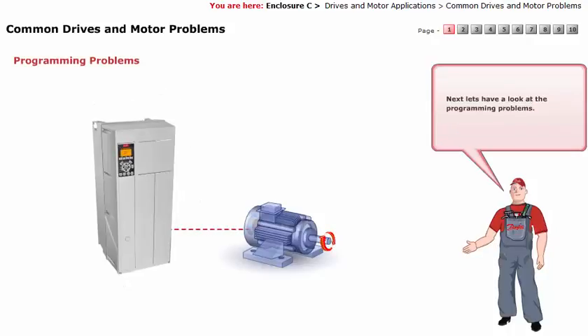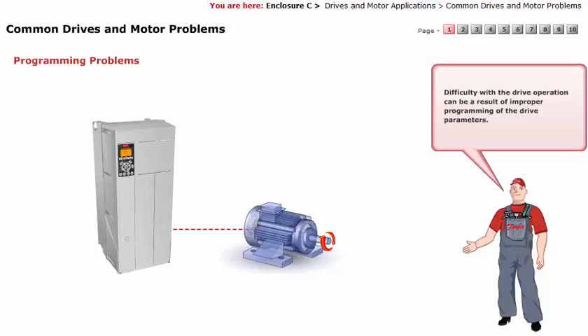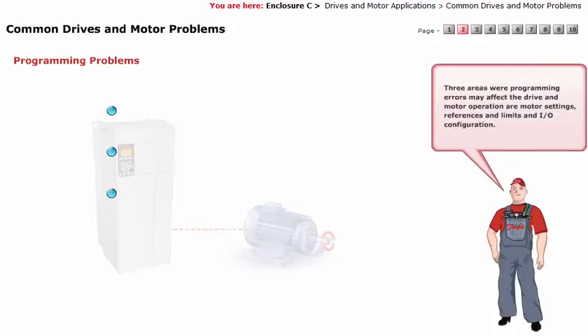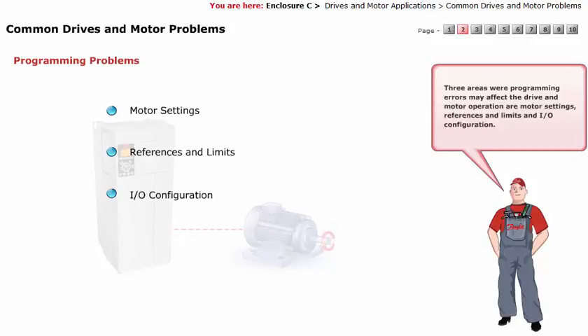Next, let's have a look at the programming problems. Difficulty with the drive operation can be a result of improper programming of the drive parameters. Three areas where programming errors may affect the drive and motor operation are motor settings, references and limits, and input-output configuration.